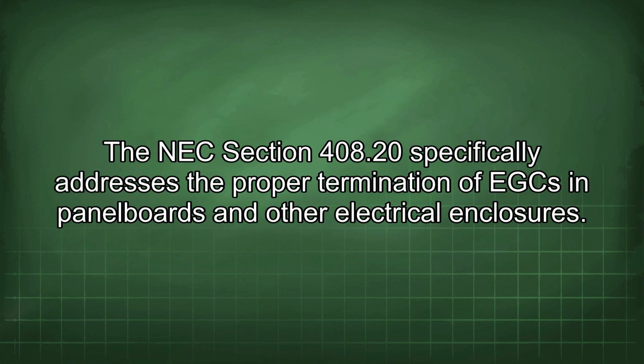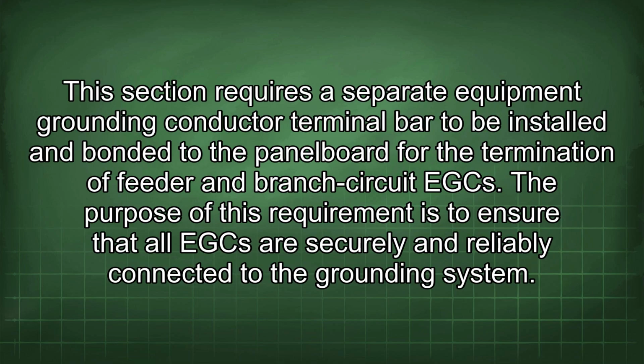The NEC Section 408.20 specifically addresses the proper termination of EGC in panel boards and other electrical enclosures. This section requires a separate equipment grounding conductor terminal bar to be installed and bonded to the panel board for the termination of feeder and branch circuits EGC. The purpose of this requirement is to ensure that all EGC are securely and reliably connected to the grounding system.